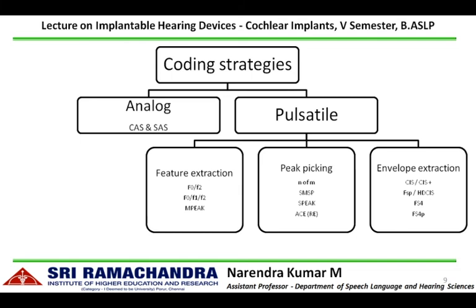F0, F2, F0F1F2, and multi-peak (M-peak) come under feature extraction strategies, which extract speech features like fundamental frequency and formant frequencies. Peak picking strategies select the maximum energy channel across different channels — the peak is picked up and only that information is delivered to the intracochlear electrode array. Envelope extraction strategies extract the channel output envelope and stimulate with biphasic pulses.